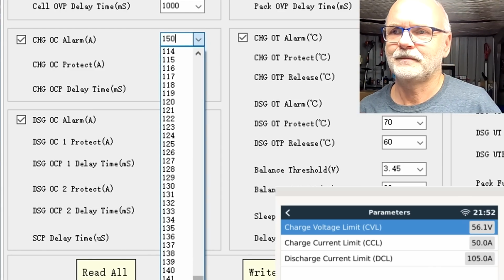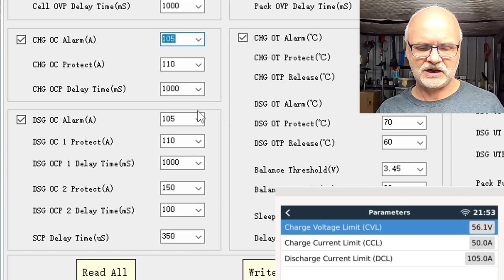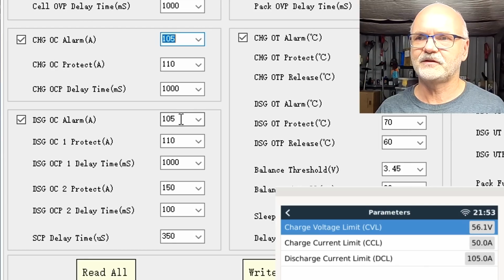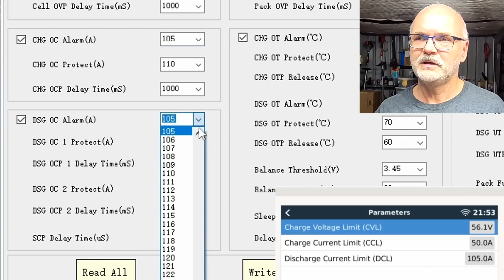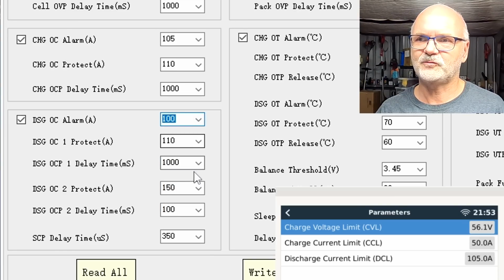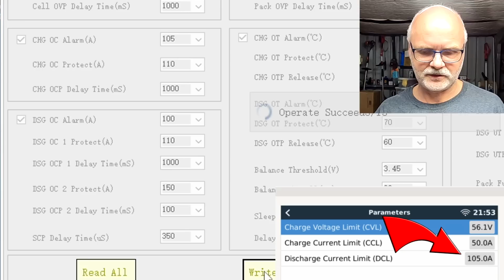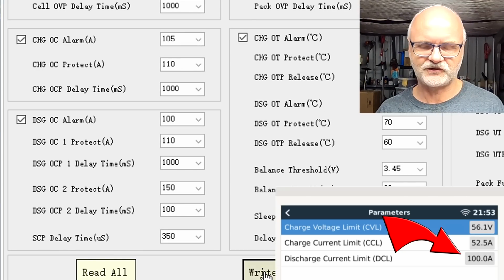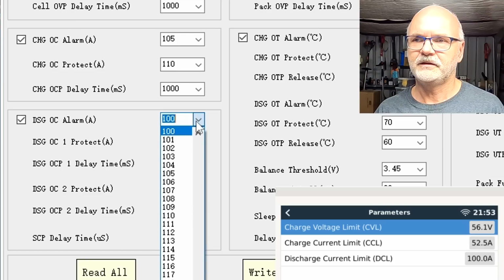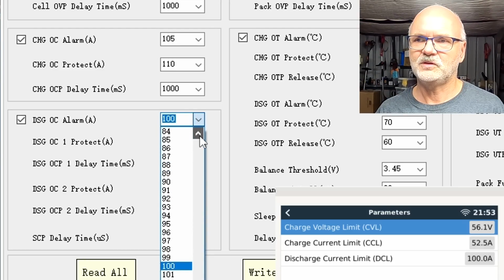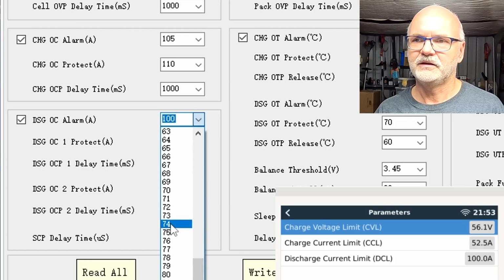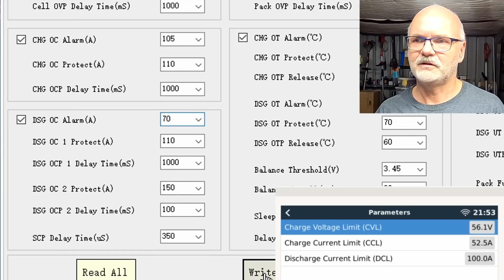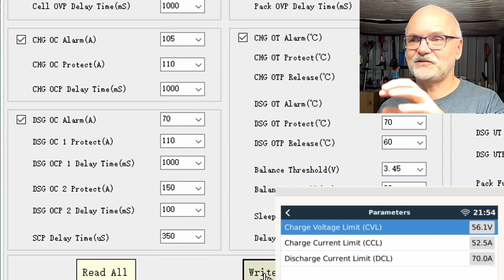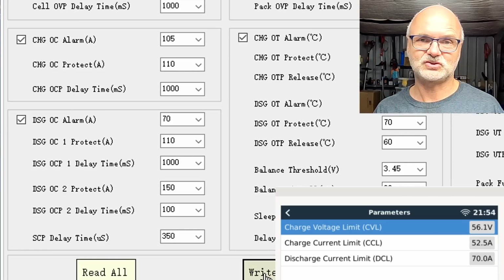I think that's okay. And we can see the last parameter, the discharge current limit is on 105 amps. And we've got the discharge overcurrent alarm sitting on 105 amps. So I assume this is the same parameter here, 1-to-1 without any formula. If we set this one to 100, we should see, yeah, it changes to 100. So this is 1-to-1. If I only want to allow the battery to discharge with, say, 70 amps.